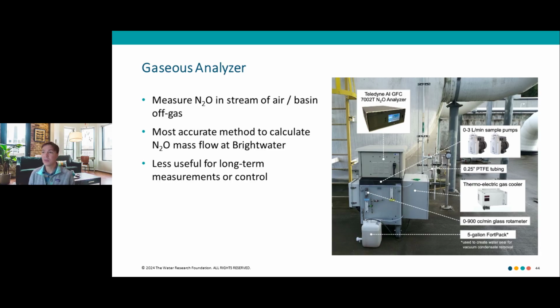The gaseous analyzer we used was a Teledyne gas filter correlation infrared analyzer. It was supposed to be an environmentally controlled enclosure. We made a pseudo environmentally controlled enclosure with a sample train to pull a sample, remove moisture and particulate, and condition it for the analyzer. The whole cart is mobile, so we can measure different locations and then take it to different plants.